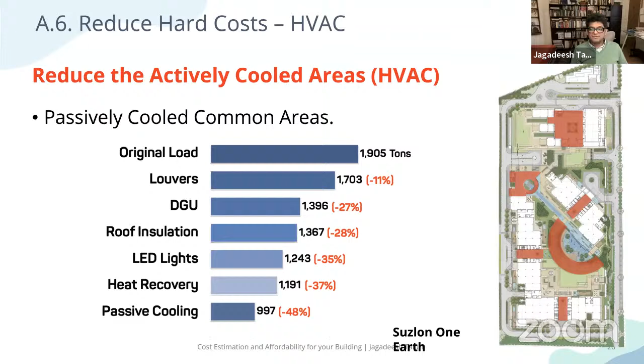One thing we did was multitask the common areas and cool them through heat recovery and indirect evaporative cooling, where we decided not to use any active means throughout the year. The thermal set point for these areas was also set to 27 instead of 24. Through this, we reduced our chiller plant size from 1900 tons to 997 tons, and we also reduced the energy consumption by 48%.